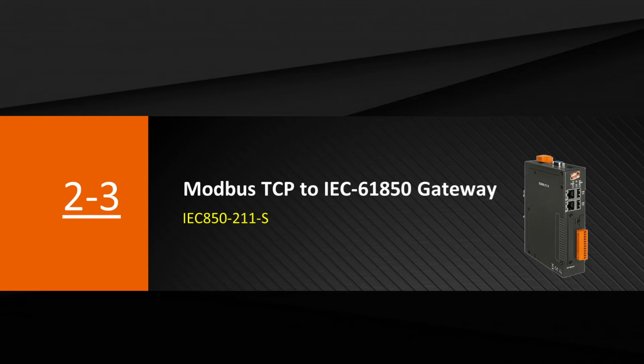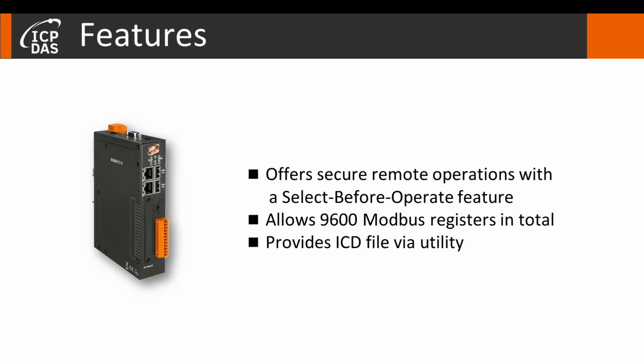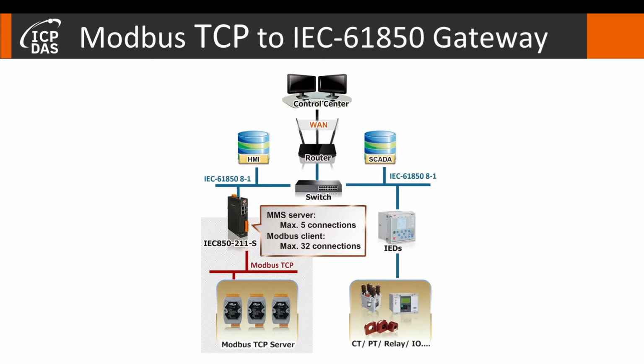Let's move to the third product, the Modbus TCP to IEC61850 gateway. It offers secure remote operations with the Select Before Operate feature, allows 9,600 Modbus registers in total, and provides an ICD file via utility. Our gateway automatically maps Modbus registers to IEC61850 data objects via utility, and allows up to 32 Modbus clients and 5 IEC61850 MMS server connections.